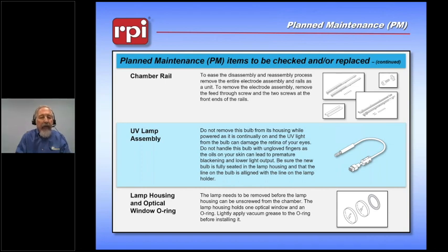Okay, chamber rails. As we said earlier, the chamber rails tend to decay over time with exposure to the peroxide. So every year we want to be sure we put new plastic wear into the chamber and they are included. There is also a UV lamp, as we talked about earlier. Please do not handle the UV lamp without wearing gloves. The oil from your skin can damage the lamp and blacken it. Make sure that you have the correct Allen wrench to remove the original lamp, it's a very small one, and that you get the new lamp in properly seated and that the line on the bulb is aligned with the line on the lamp holder.